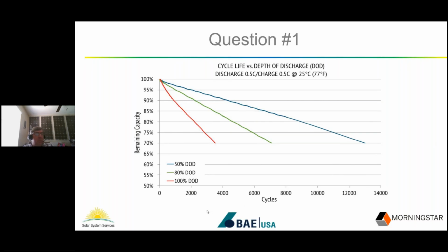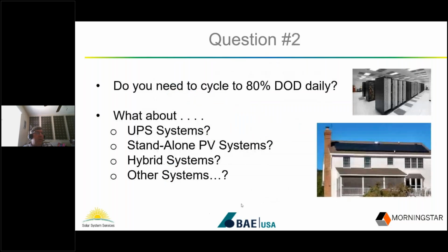I start out by talking about depth of discharge, because this brings up my second question: do you need to cycle at 80% depth of discharge every day? If you're looking at a UPS system, you may only use it 5 times a year.